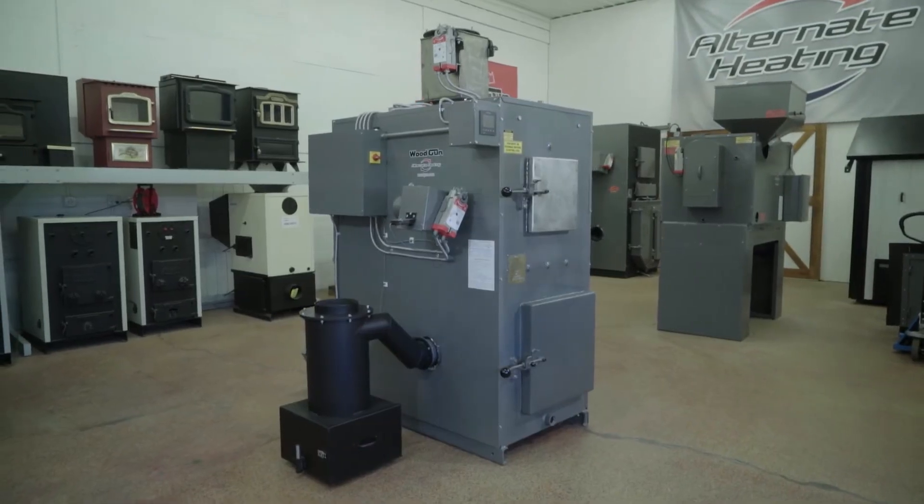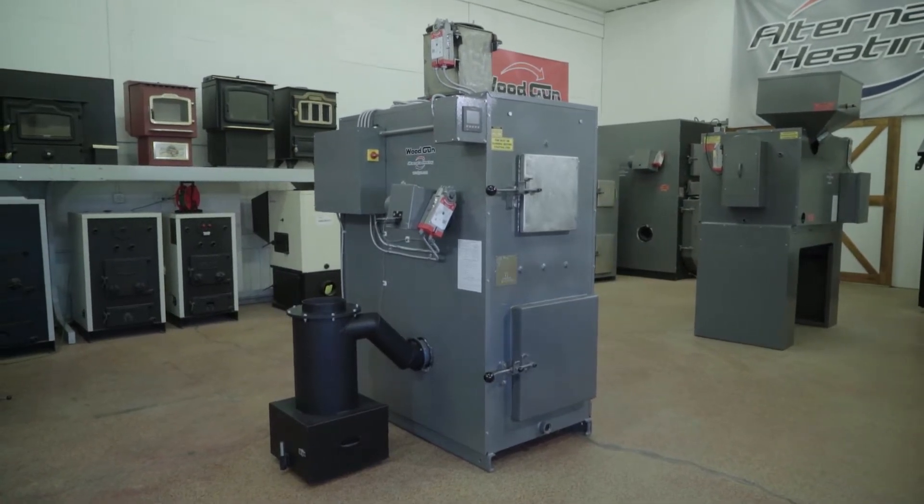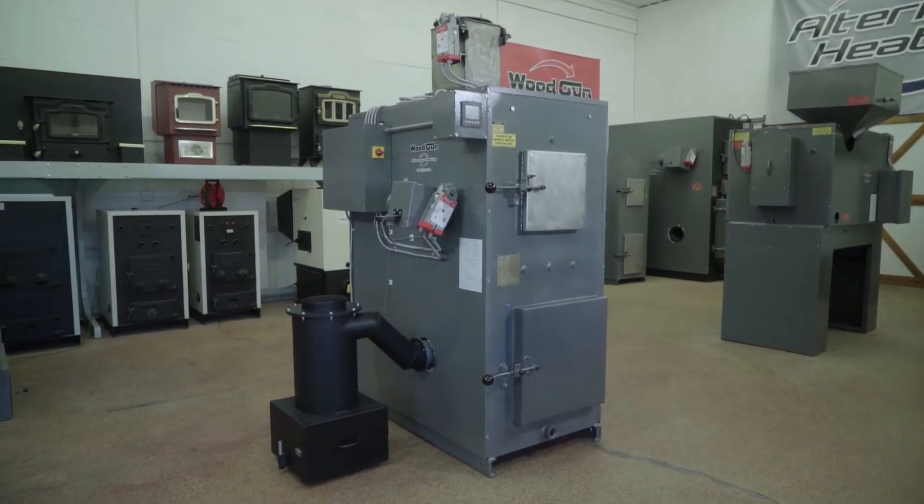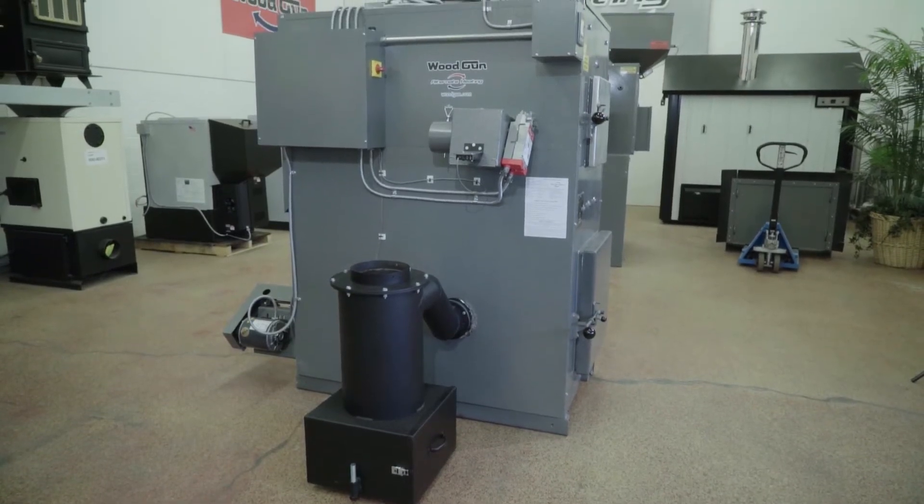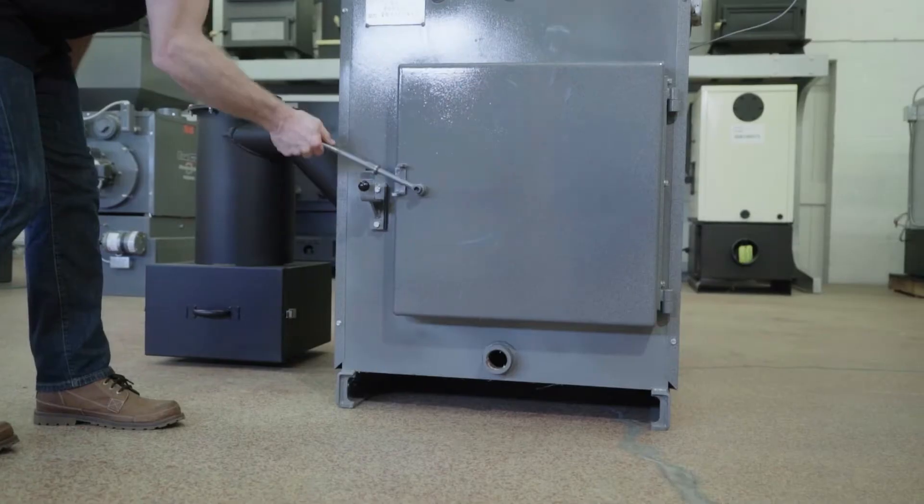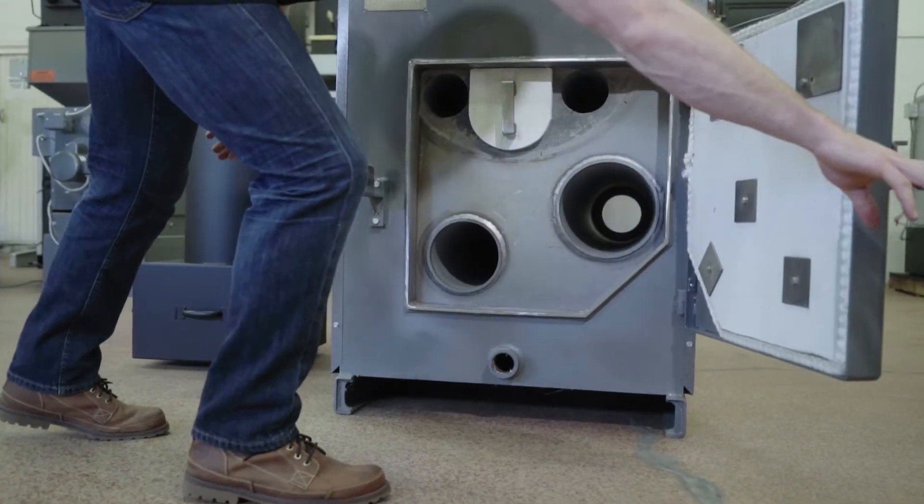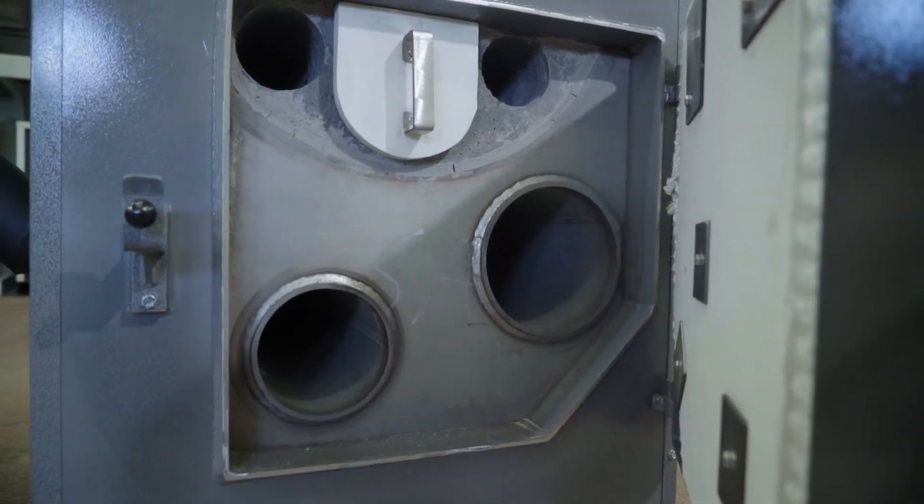The E250 Wood Gun is a wood gasification boiler and it is a true downdraft gasification system. You burn 60% less wood than your traditional wood boiler, and we do this by using refractory. This refractory captures the flame and runs it through a set of tunnels which burns the smoke or wood gases, which allows us to use 90% of the wood.